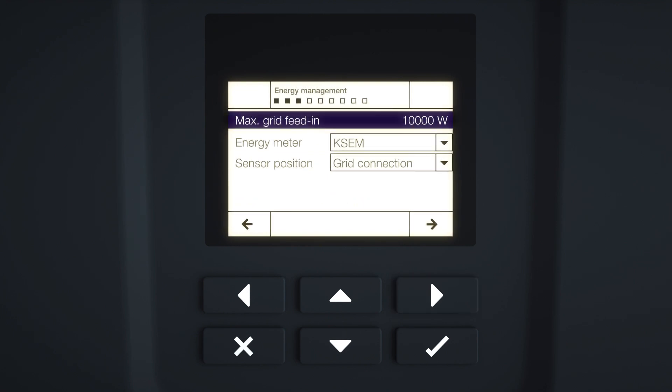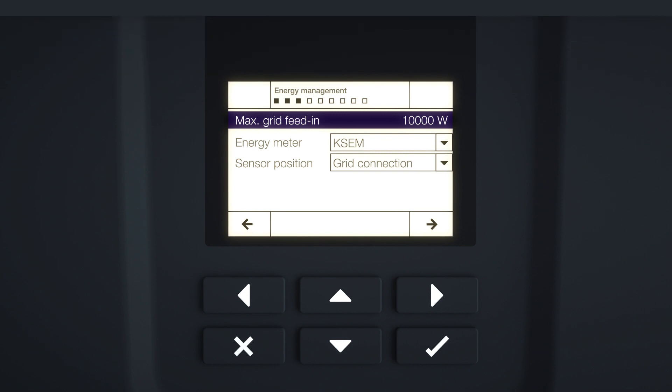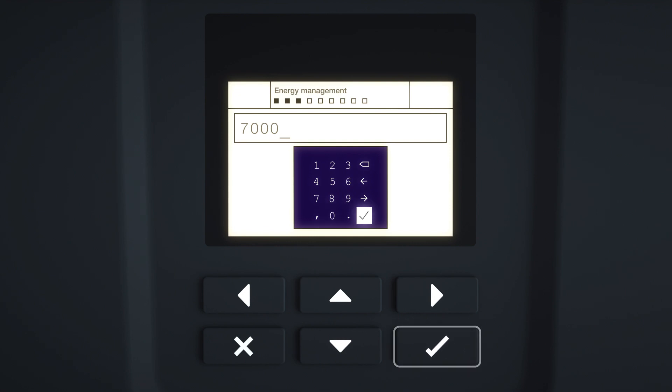The energy management menu is displayed. You can place a limit on the maximum grid feed-in here. In Germany, for example, this may be 70% of the connected PV generator capacity. To do this, press Enter and use the arrow keys to enter the value you want. Confirm each digit with Enter. Once all digits have been entered, confirm by selecting the tick symbol.